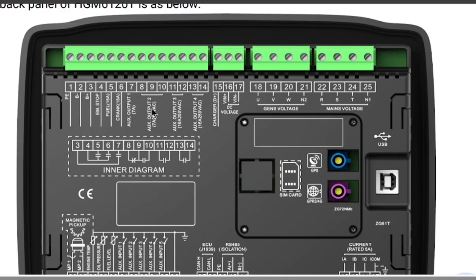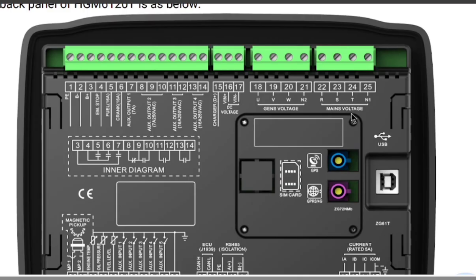This is the 220 volt AC supply output. Okay, as you can see, this is the system output, maximum 7 ampere, and this is the 220 volt AC, maximum 7 ampere, 220 volt AC. This is the 12 or 24 volt, your system voltage, and this is your AC voltage, which you require for something to operate the contactors, the main contactors. And so let's move. As you can see here, we also have 250 volts AC auxiliary output. Okay, 13, 14, and pin number 15 is the charger alternator dynamo plus input.